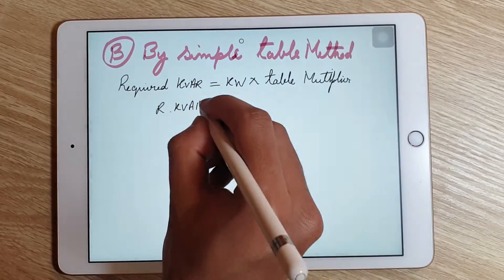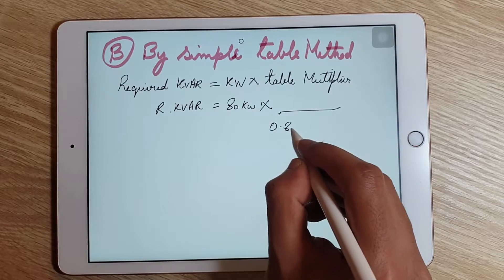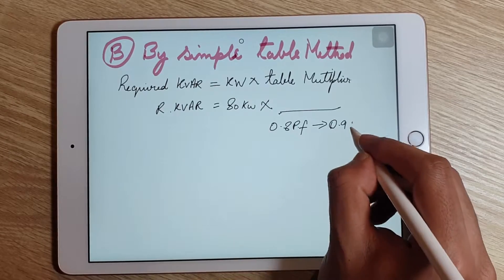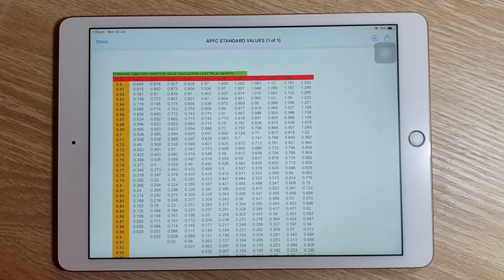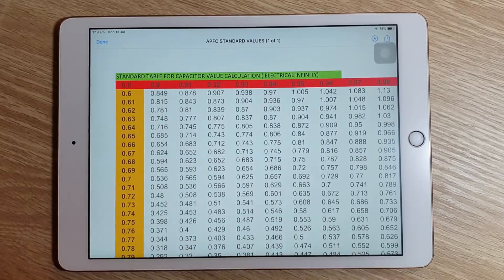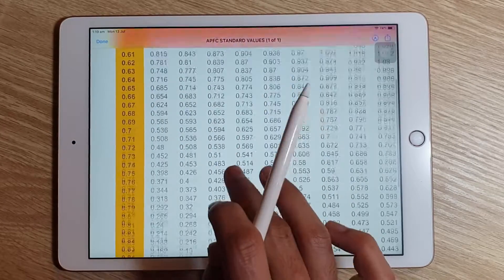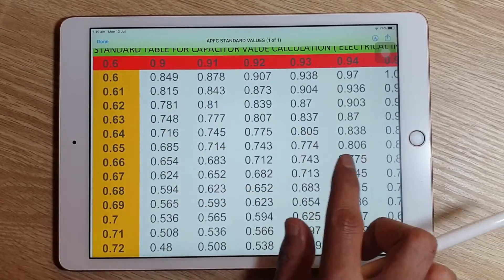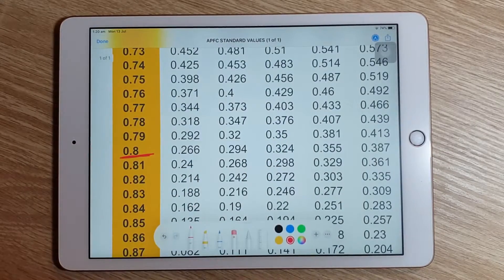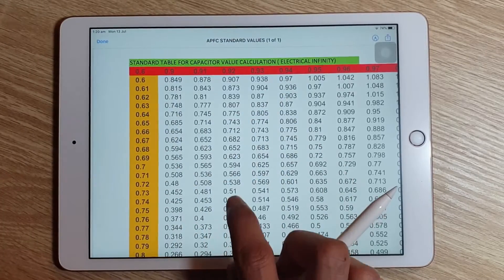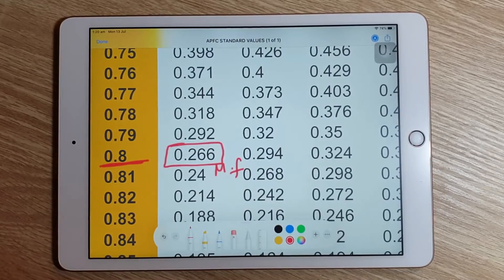Substituting the values: we have a kilowatt value of 80, and we need the table multiplier. This multiplier depends on the required power factor of 0.9. Looking at the table — with the measured power factor on the left in yellow and the required power factor across the top in red — for a measured power factor of 0.8 and required power factor of 0.9, the multiplying factor is 0.266.